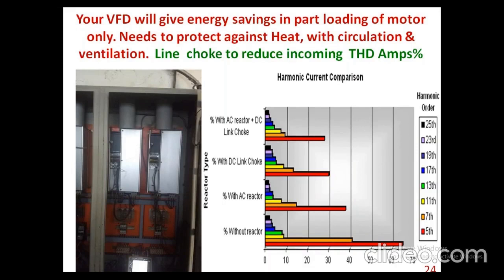A combination of an AC reactor and a DC link choke, you can see the graph on the right side, will definitely bring down the H5 component from around 60% to less than 28%. This is how you arrest the harmonics H5 and H7, by having this line reactance choke. This is more important, and very much applicable to all the ring frame machines. If you are overloading the machine, this harmonic choke will not help, because it will reduce the voltage at the input. If you are partly loading the machine, the line reactance choke is a mandatory thing, and you can suggest to the textile mill to add the line choke at least at the point where the harmonics are going up, so you get it arrested there.